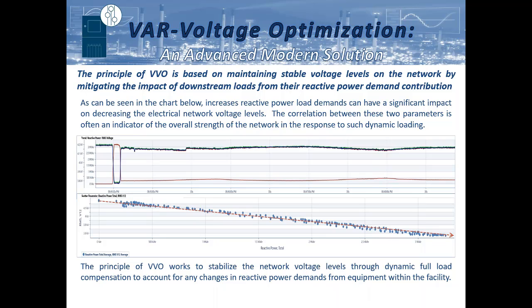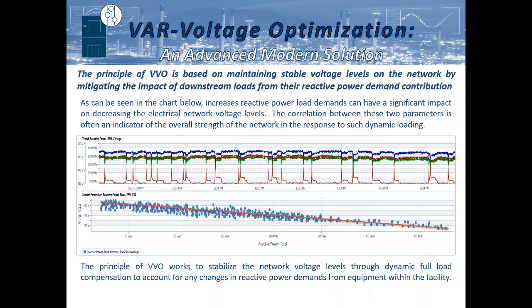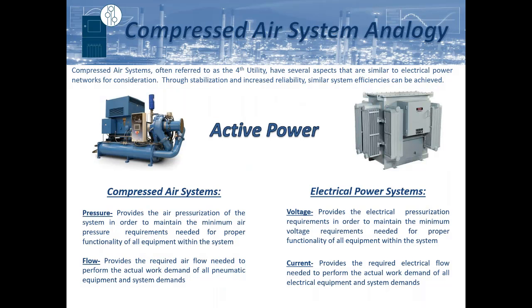But you can see in this graph right here, we've actually charted both the reactive power as well as the voltage. So you can see as the reactive power increases, it has a direct impact on the nominal voltage on the network. And in the lower graph, we've charted the RMS voltage versus the total reactive power, and you can see the strong correlation here. And it's not only for medium voltage, this is for low voltage as well. This is an office building where you can see the elevators constantly being engaged and disengaged, and that having a direct correlation with the voltage as well. So what the equalizer system does is compensate for that in real time.